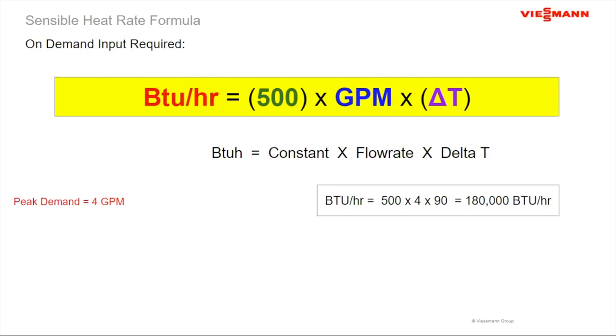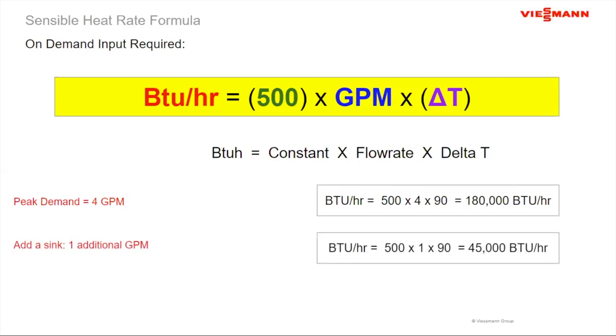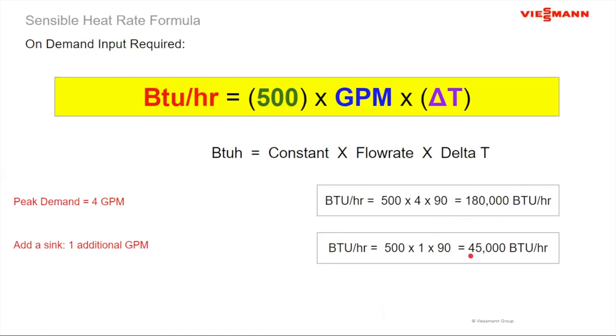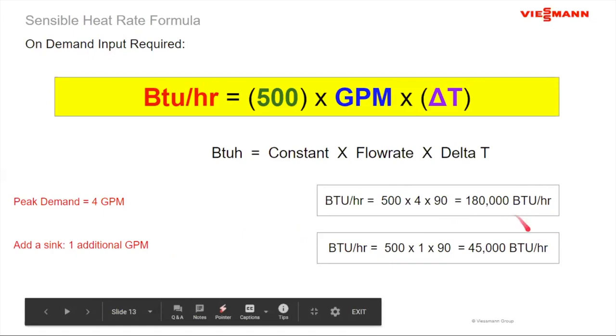Now, I just want to throw something at you if I come up short in my calculation. Let's say that we calculated that we need 4 gallons a minute, but during that draw period when both showers are running, let's say somebody decides to do dishwashing down in the kitchen and they're using water at the rate of 1 gallon per minute. That additional 1 gallon per minute represents an additional 45,000 BTUs of energy, okay? And you'll find the number for 1 gallon probably wavers, depending on the delta T, anywhere from about 38,000 to 45,000, depending on the delta T you're looking for. So all of a sudden, if the requirement really isn't 4 gallons per minute, it's 5 gallons per minute, I don't need 180,000 BTUs. I need 180,000 plus 45,000 or 225,000 BTUs.